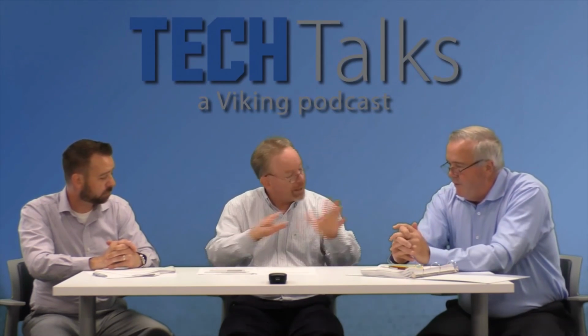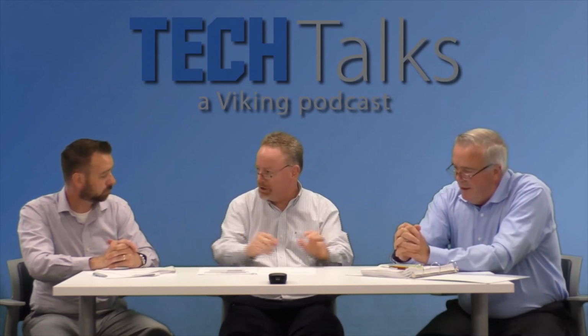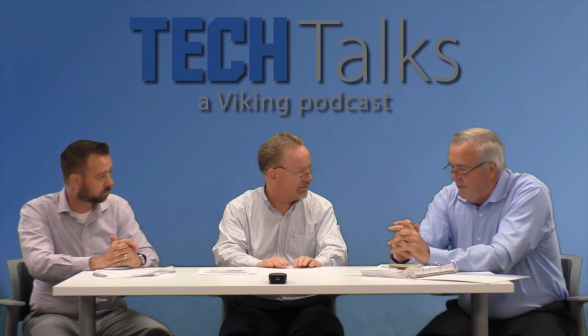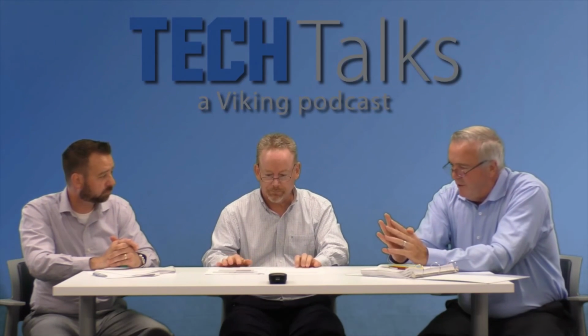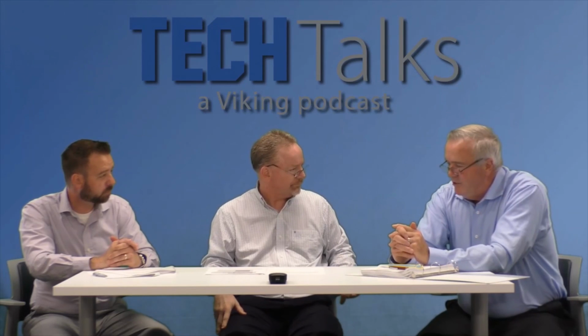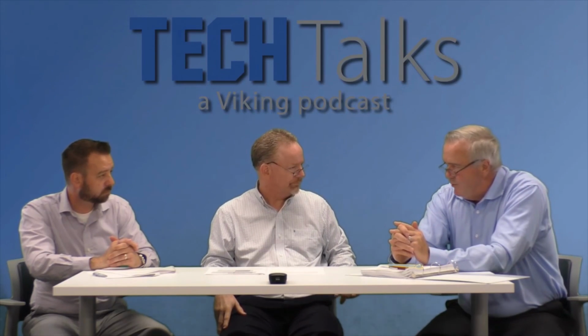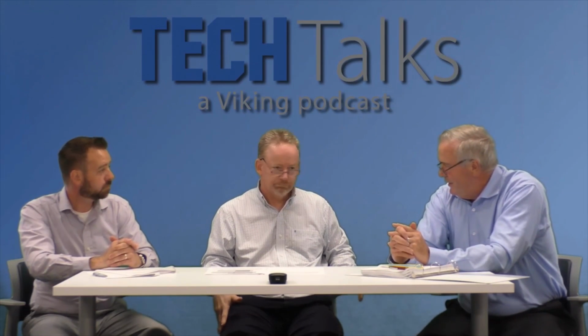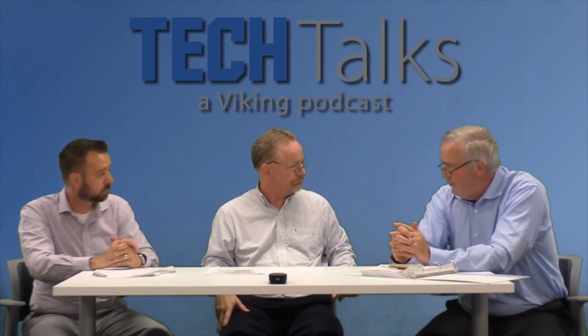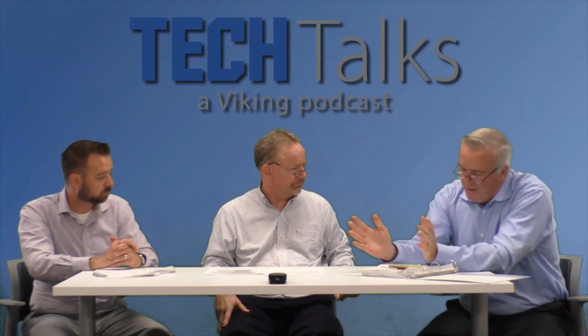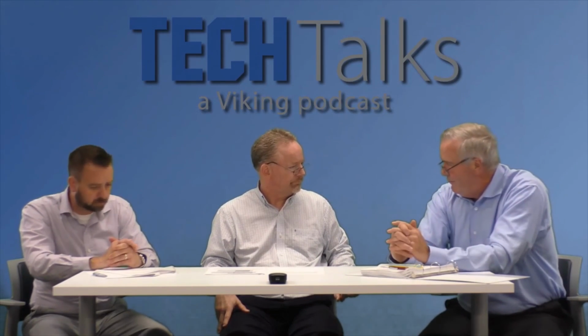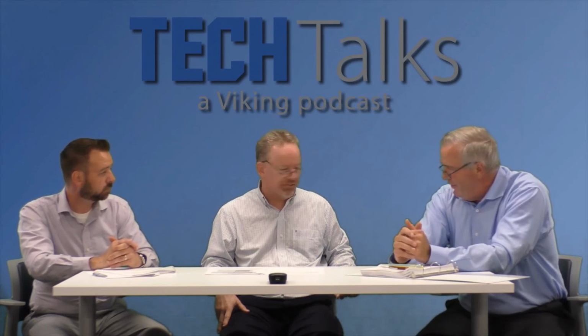So before we do that, let's get to any concluding thoughts that you guys have. I know people are reading the table, and there is one advantage of the K33 over the K28, and that's at a 55-foot ceiling, where they have a 6-foot aisle and we have an 8-foot aisle. Right. So if that's the advantage, then that's great for the above 50 to 55. Above 50 feet, right. Sure.